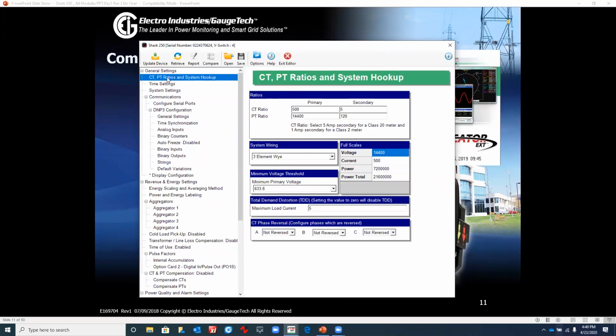So the CTPT compensation is very important. When you program the meter, you need to have firstly a one line or some kind of a diagram showing how the metering is going to be configured. You reference that to enter this information. You would pull that information. So in this particular case, from the drawing, I saw these are 500 to 5 CTs.